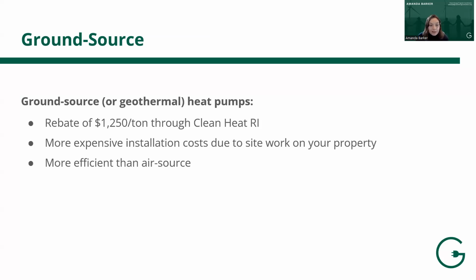I do want to call out the ground source heat pump system, which is less common than air source systems. There is a rebate through Clean Heat Rhode Island for $1,250 per ton, as mentioned previously. But one thing to note is that ground source systems are more expensive to install, because you need a backhoe onto your property to dig and lay the refrigerant line into the ground. However, they are more efficient than air source heat pumps, so if you have the space, it's a good option as it will save you on operating costs due to its greater efficiency.